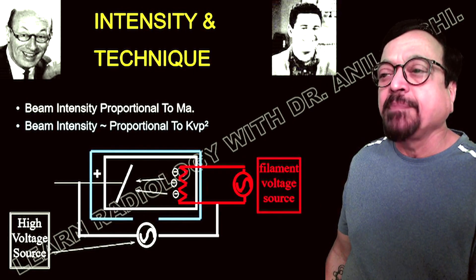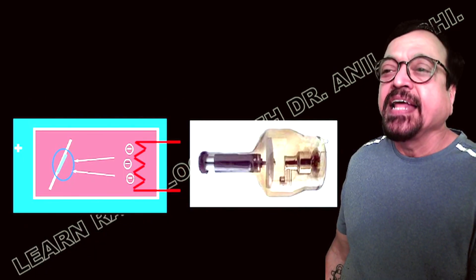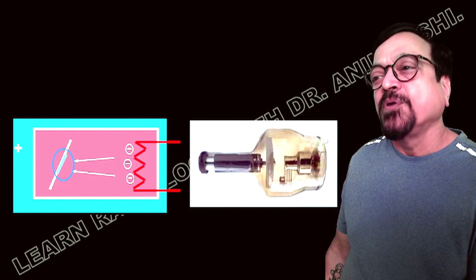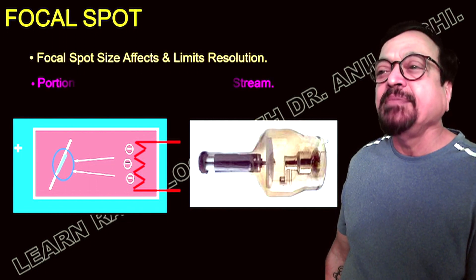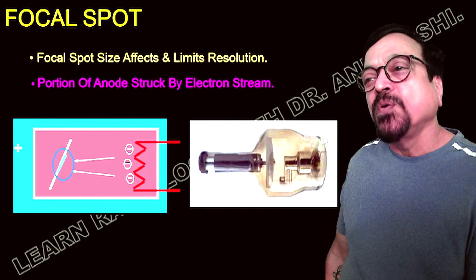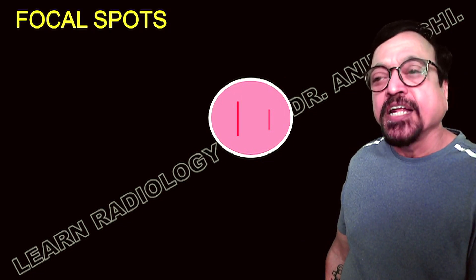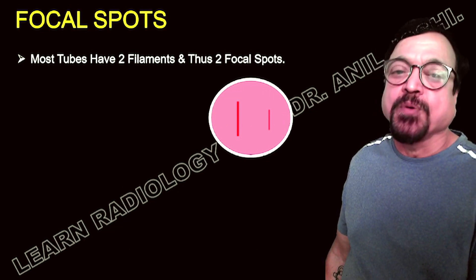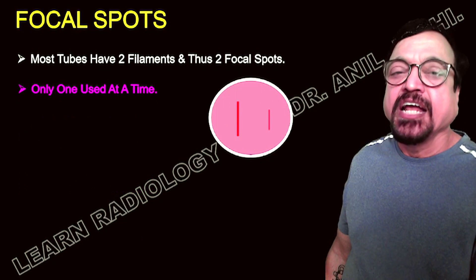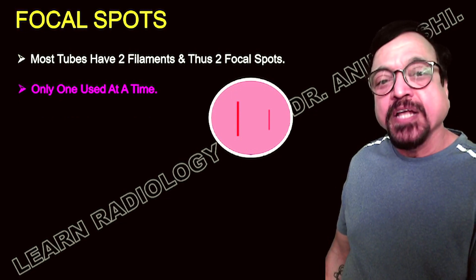Beam intensity depends on kV, mA, target material, and filtration. Beam intensity is proportional to mA, and proportional to kVp squared. High voltage is applied to the filament which releases electrons; they are then accelerated and x-rays are produced. The focal spot is the portion of the anode struck by the electron beam, and its size affects and limits resolution. Most tubes have two filaments and thus two focal spots — one small and one large.